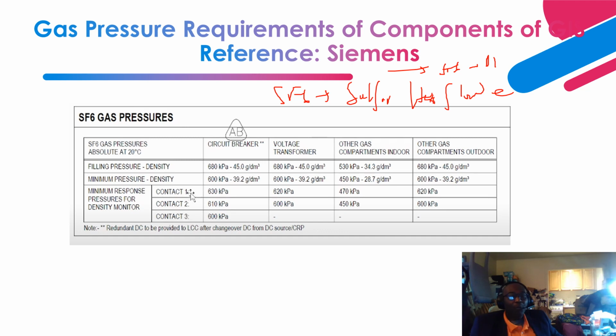So this table basically gives you a typical filling pressure for the different components. It tells you the filling at 20 degrees Celsius. This is at the factory level, where the manufacturer is able to simulate and obtain a factory temperature of 20 degrees Celsius. What the manufacturer gives you as part of its instruction and operating manual are the SF6 gas pressures at different temperatures.